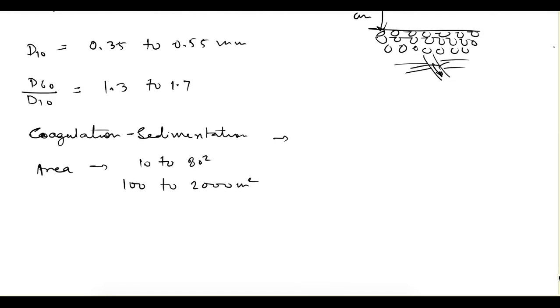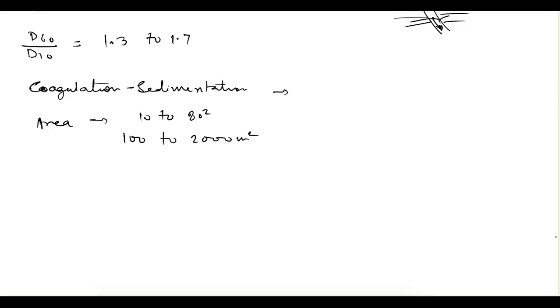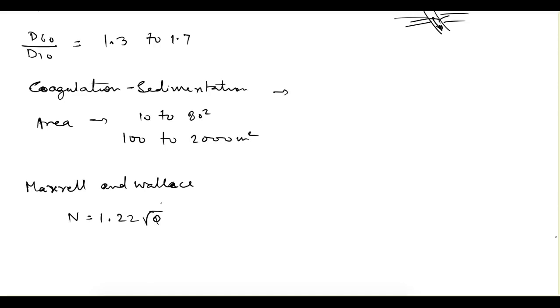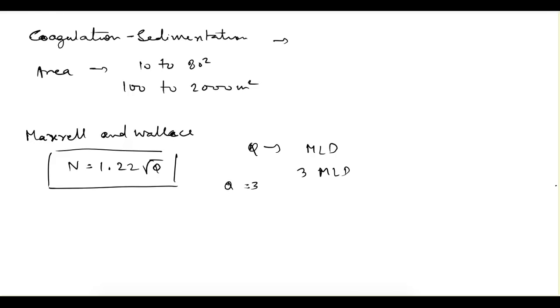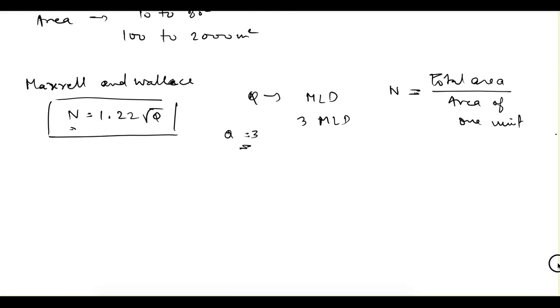The space requirement for slow sand filter is much higher. There is one equation used to find the number of filters, given by Morrell and Wallace: n is equal to 1.22 times the square root of Q, where n is the number of filter units and Q is the flow in million liters per day. For example, if the flow is 3 MLD, then Q equals 3. However, if total area and area of one unit are given, you can simply find n by dividing total area by area of one unit.